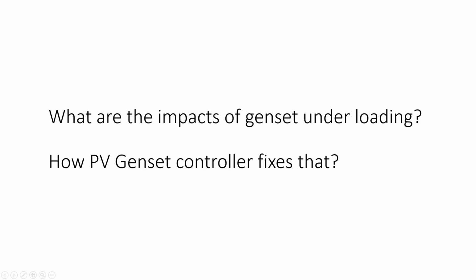What are the impacts of genset running in underloaded condition? How does the PV Genset controller fix that? By the end of this video, you will get to know the implications of a generator running in low or no load condition. This also covers how wet stacking of a generator set is handled by the PV Genset controller once grid-tied solar is integrated into the system.